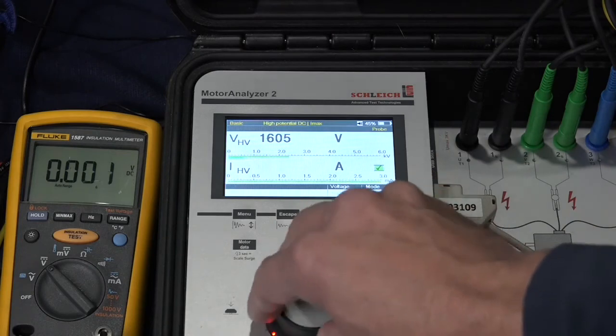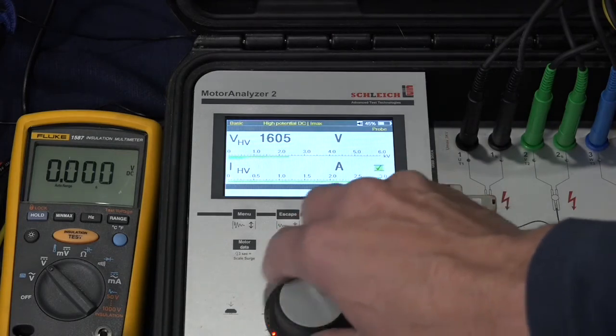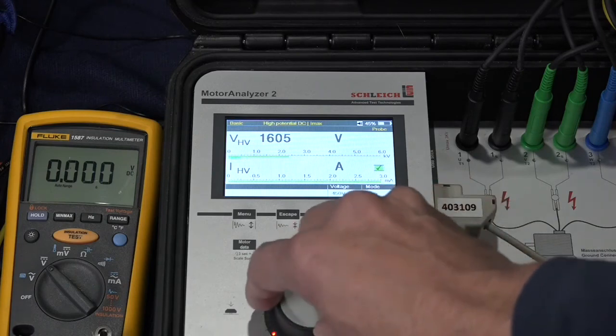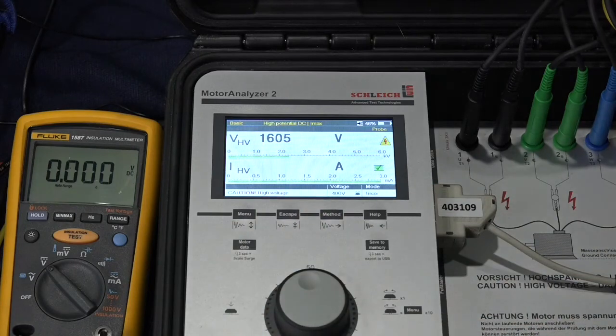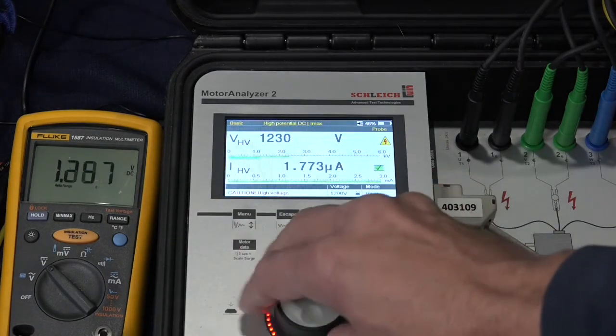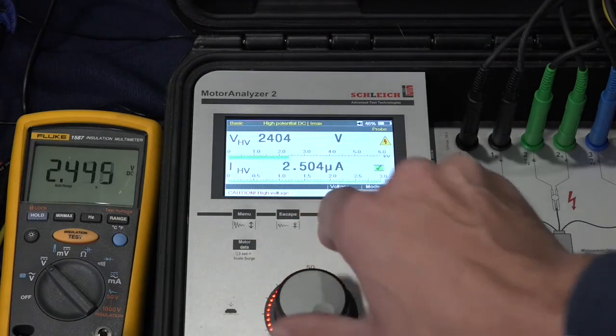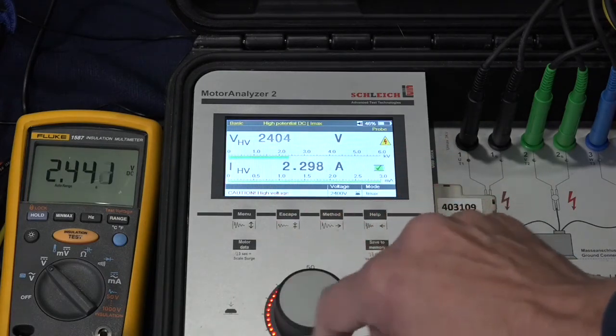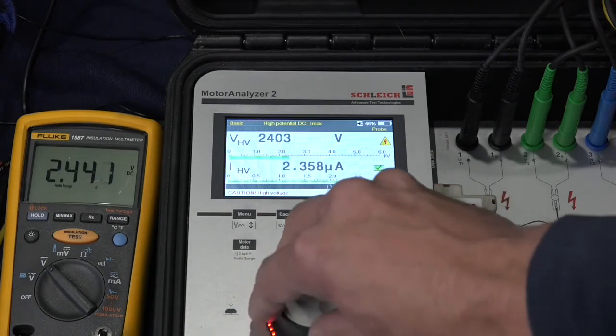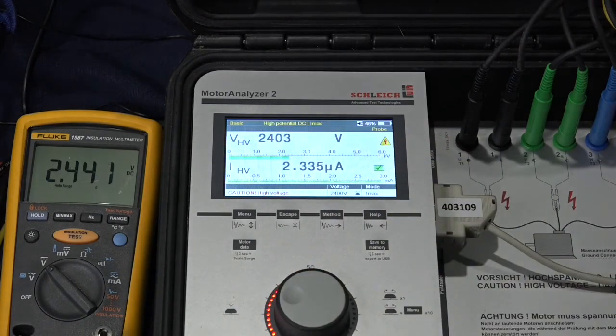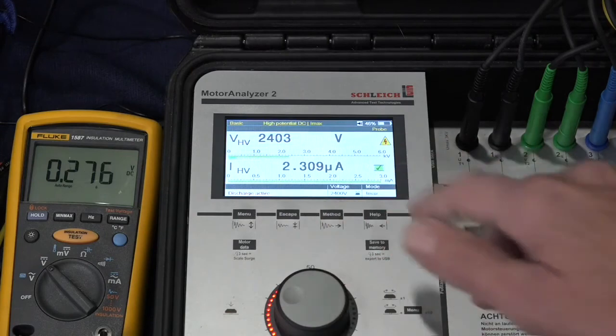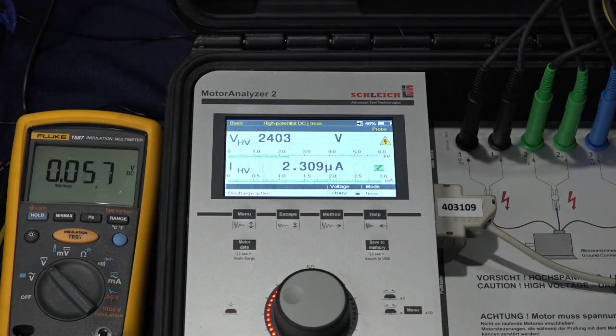Now what I can do on this screen is actually, before I begin the test, control the voltage at which it starts at. So let's set it for, say, 400 volts. I'll start the test, and it automatically goes to 400 volts. And then I can control the voltage up and go a little higher. But notice it's not going to let me go past 2400 volts. I can spin this wheel all I want, but I'm not going to be able to go past. Let's stop that test. Again, you'll watch it discharge. While it's discharging, you'll hear a little buzzer that the instrument has making a sound just to indicate that it's discharging the windings.